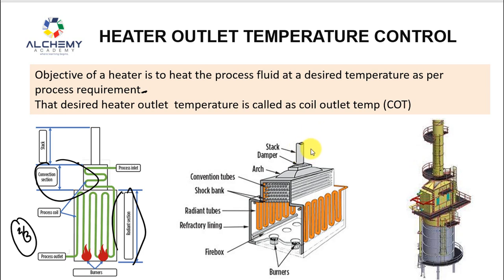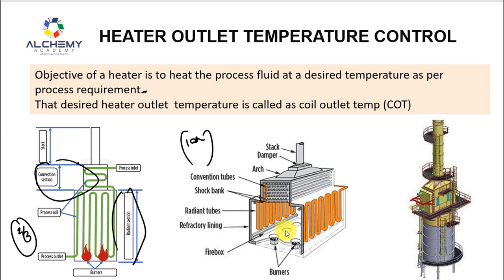Now, coming back to the control philosophy. For a natural draft heater, draft means: outside pressure is one atmosphere, and inside the firebox you maintain slightly lower pressure. That pressure difference is called the draft. If draft is maintained, the fire is contained in the firebox. If draft is lost, the flame can hit the tubes and come through the peep holes, potentially burning or radiating heat onto the person doing field rounds. So we must monitor draft from the DCS control system.